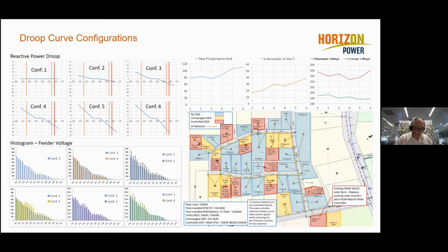The 3 graphs on the upper right-hand side, and this is the bit that you want to keep an eye on, show the maximum power exported by this feeder back into the main network through a single point of connection, the steady increase in the amount of reactive power absorbed by the inverters under test, and then the average maximum and minimum voltages on the feeder under test.